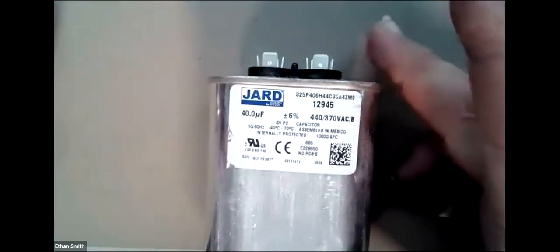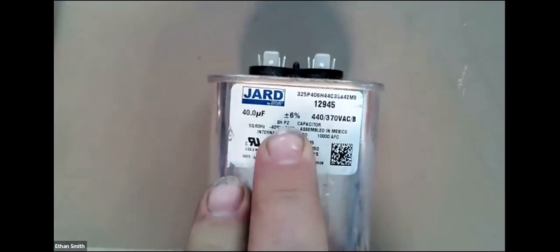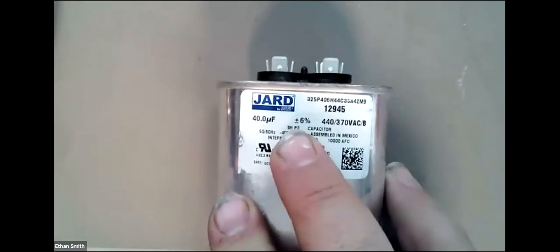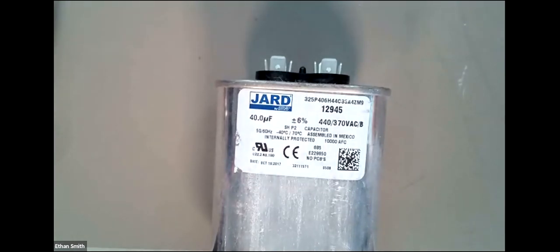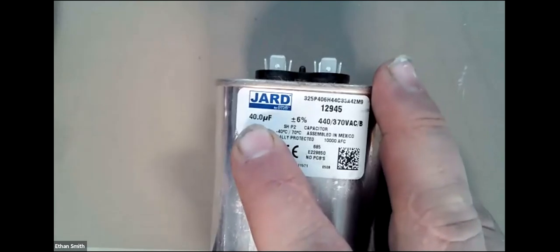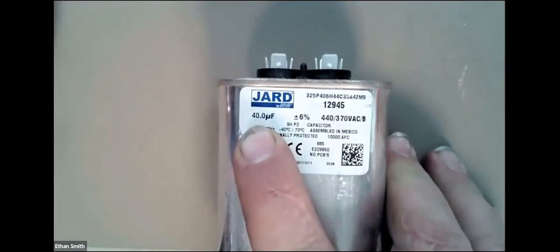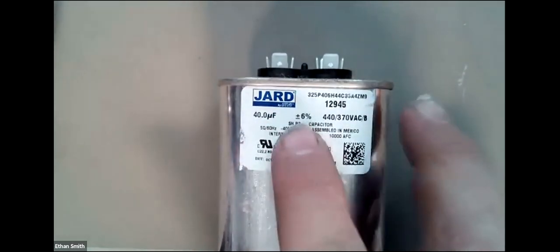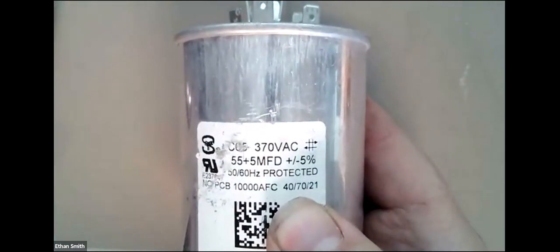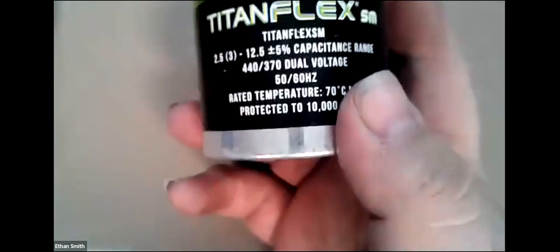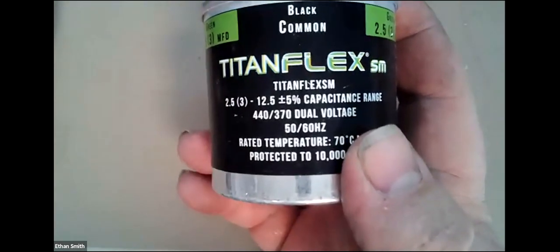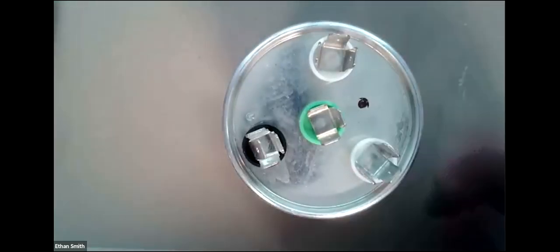So here's another one. This is a little different brand of capacitor here. This is a 40 microfarad capacitor, plus or minus 6%. So how much range do I have on that one, guys? 2.4. So I could be as high as 42.4 and as low as 37.6. Quick math. But everybody's capacitor is going to be a little different. That's a plus or minus 6. As they get bigger, sometimes that tolerance increases, but here's a 55.5 plus or minus 5. Again, plus or minus 5. And I don't know if this one shows it. Yes, this one does. So this is a multi-tap capacitor, and that's plus or minus 5%. So universally, the rule of thumb on capacitors is plus or minus 5%, you're good.